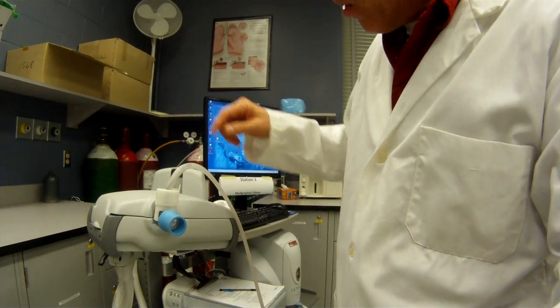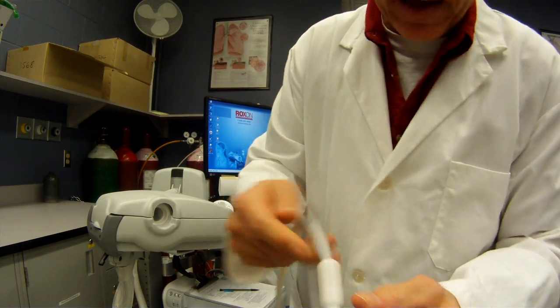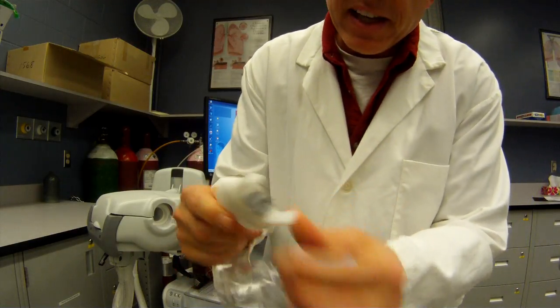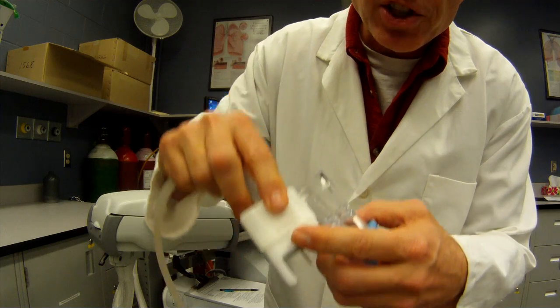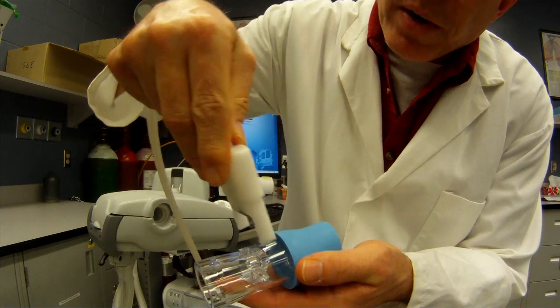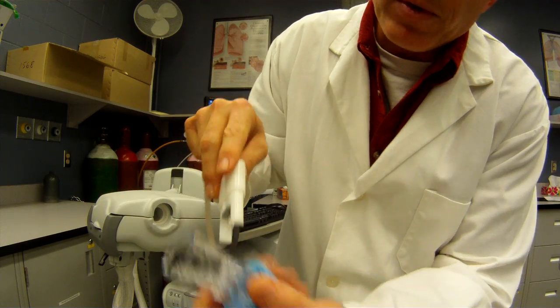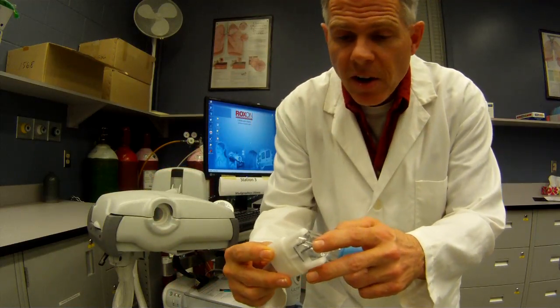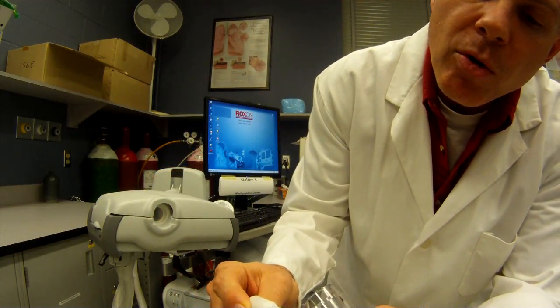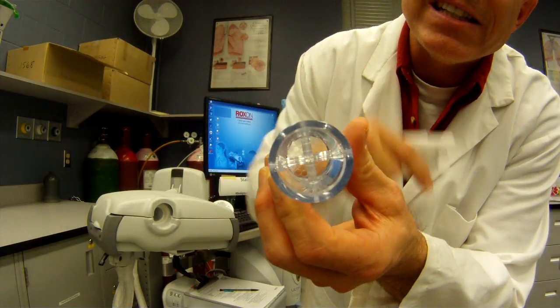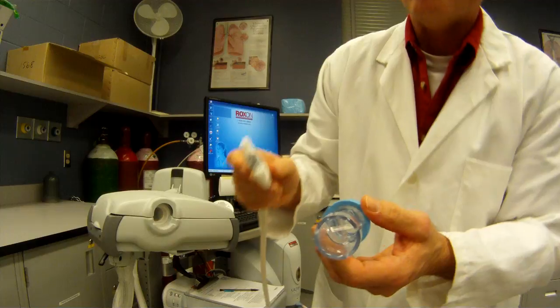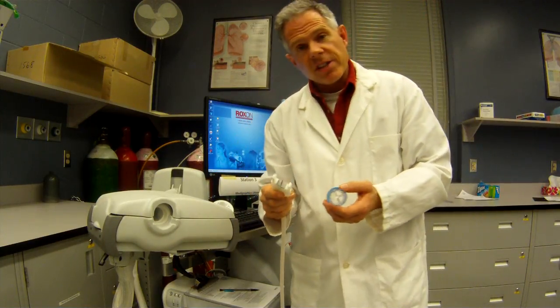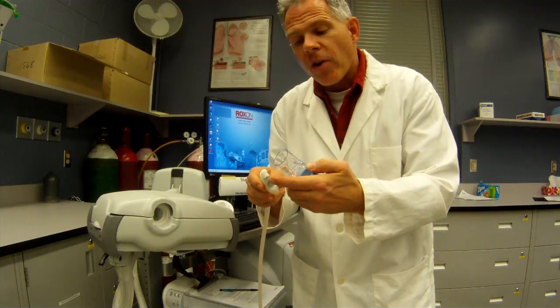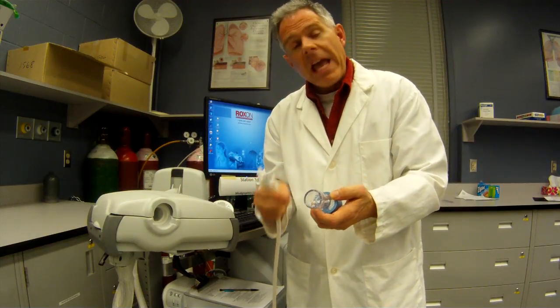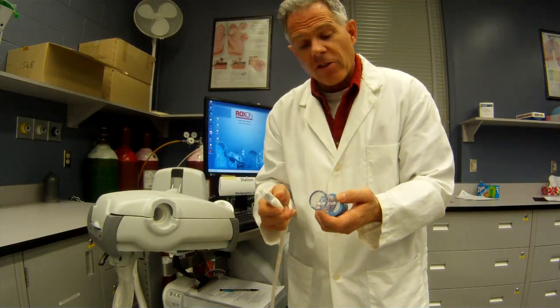Now, this little component right here is our pneumotach. It's important that you plug this in correctly when you're hooking it up. There's a little notch in here that has to line up with a little notch right here. And these little tubes have to line up with little holes also right in here. This is the heart of the device. This pressure drop across here, caused by that little bit of resistance inside, is how this device measures flow, pressures, and volumes. By measuring the pressure drop across that known resistance, it can calculate the flow. If you know the flow for a specific period of time, that tells you the volume.